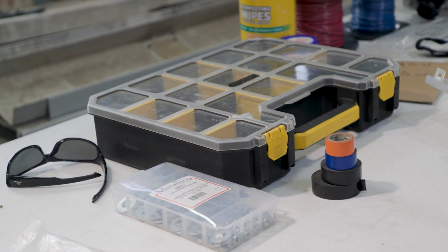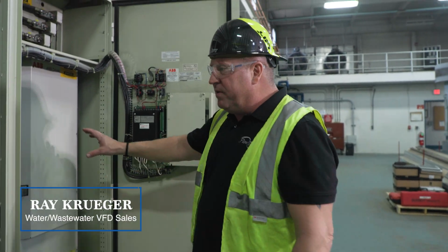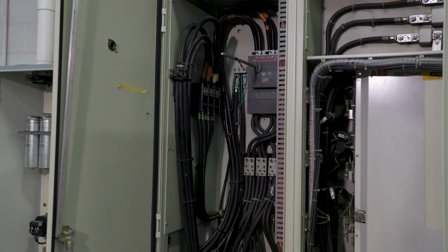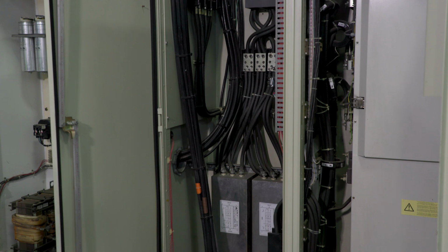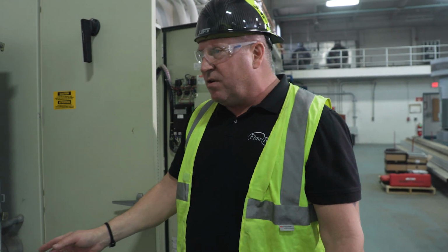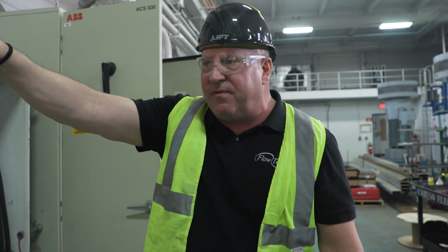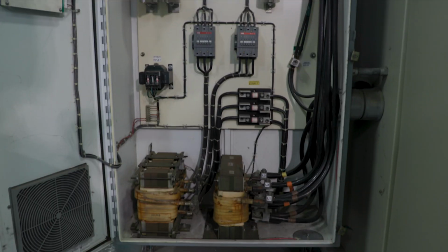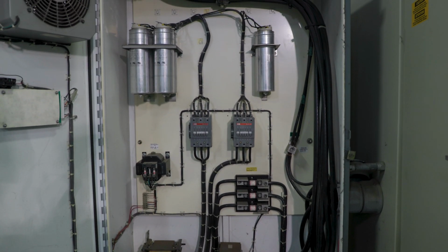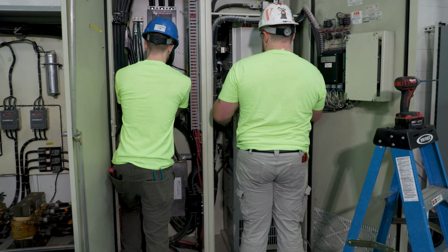One guy will get over here, he'll start removing the drive. We'll get one guy in here, he'll start removing the EMI filters and some of the wiring. And then we'll get probably 2 guys over here. We have to remove the fans. We're replacing the fans and the harmonic trap filter. We're going to strip this panel down, the complete panel down, and rebuild it. It's about a 3-day process.